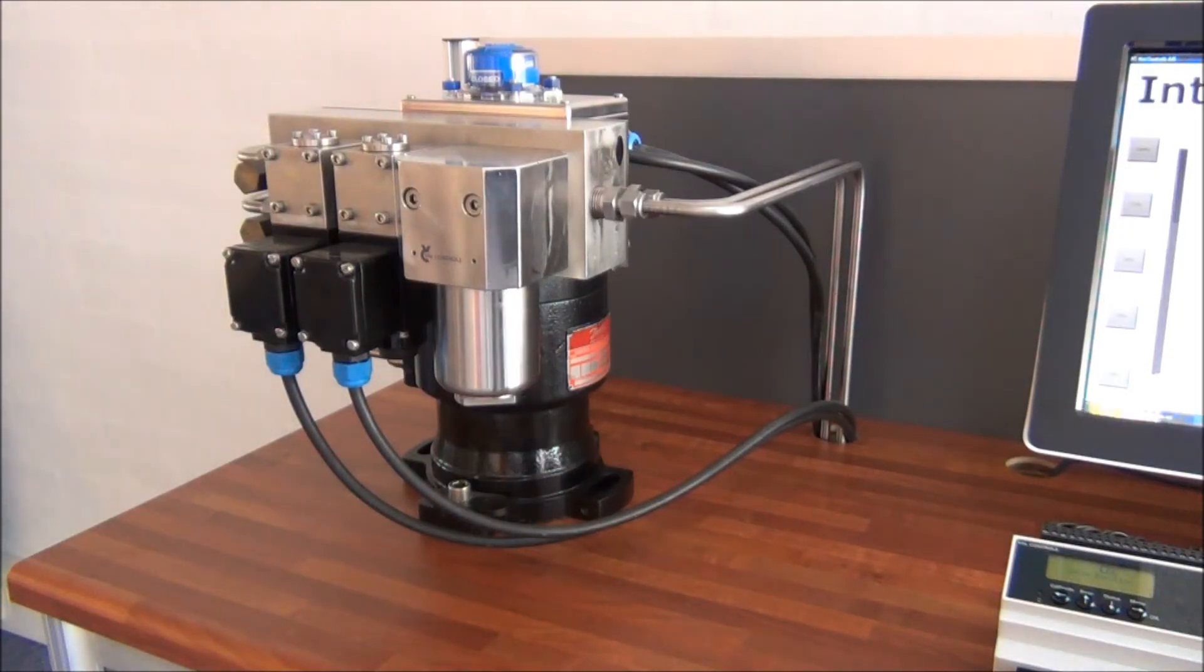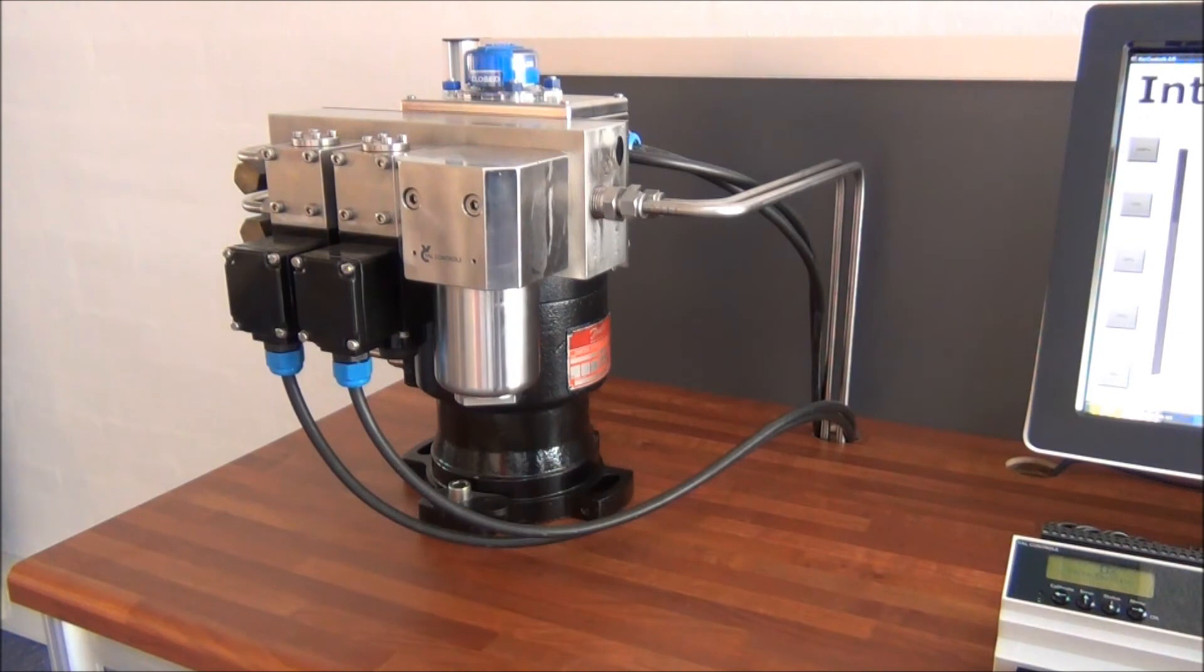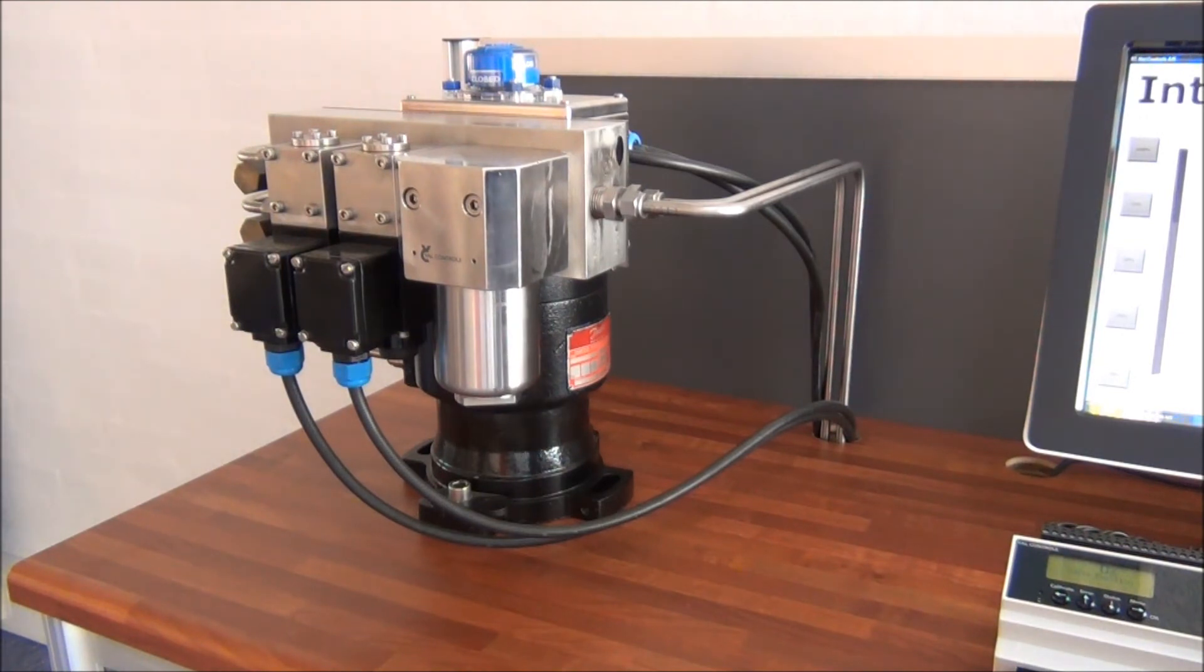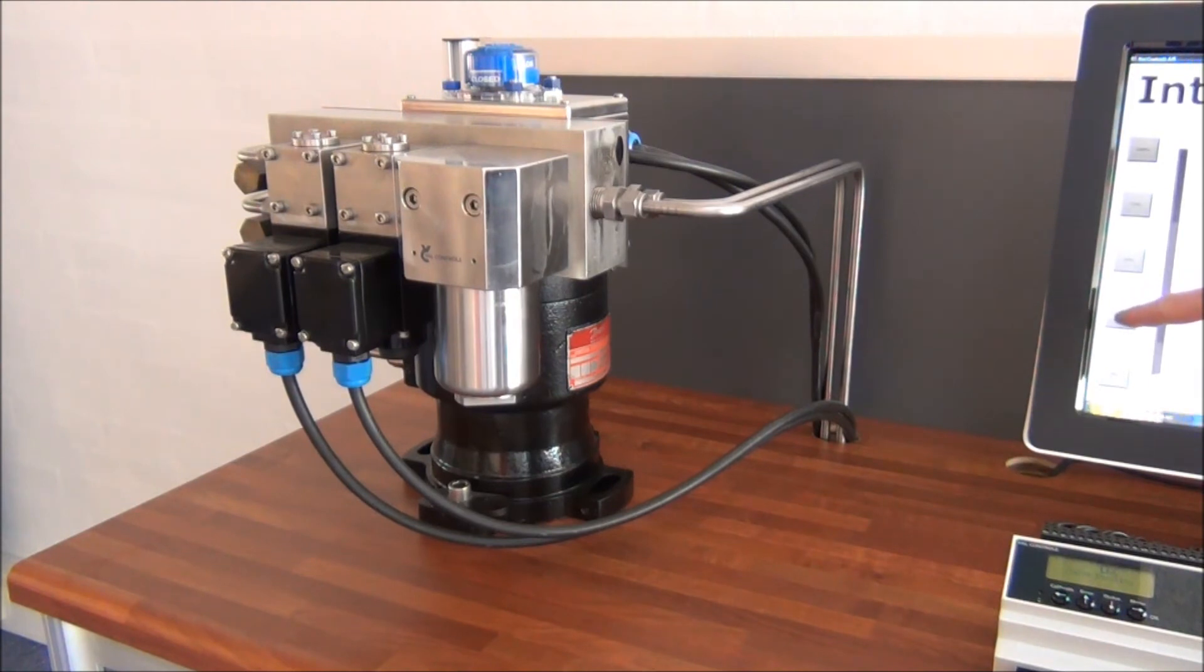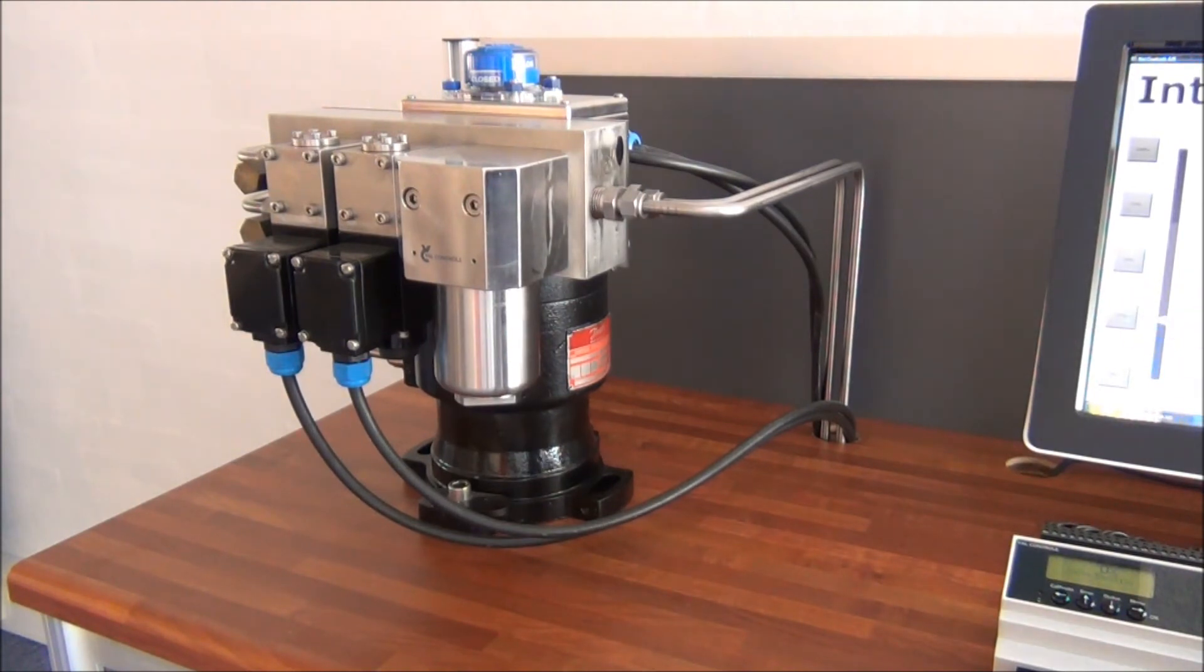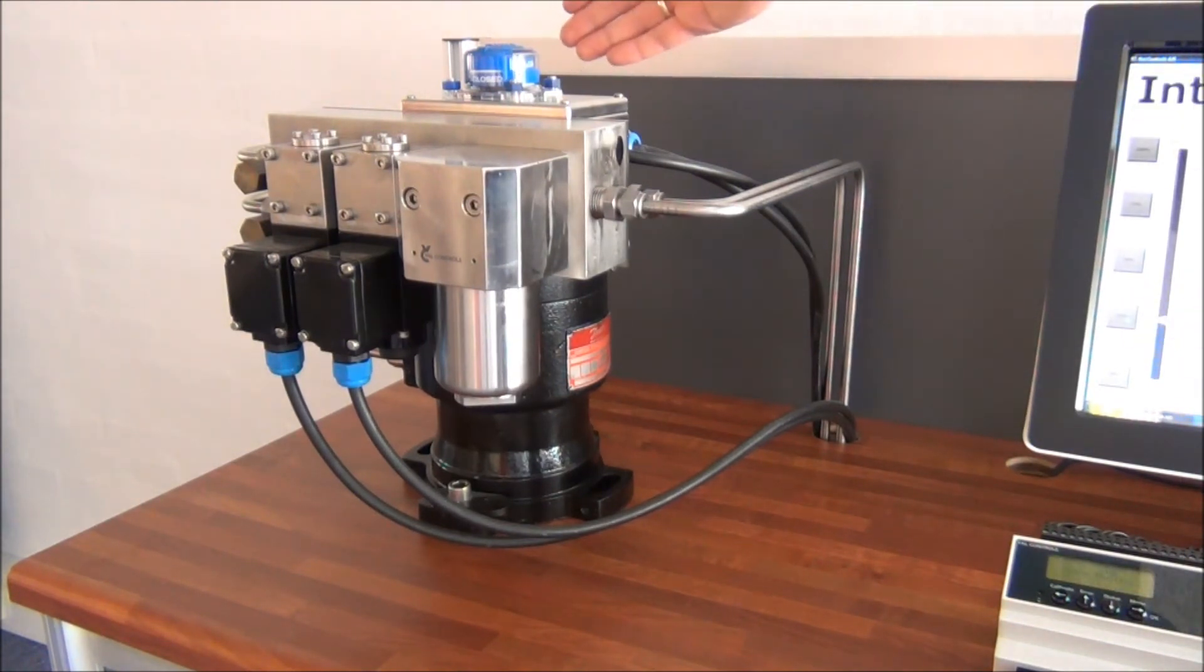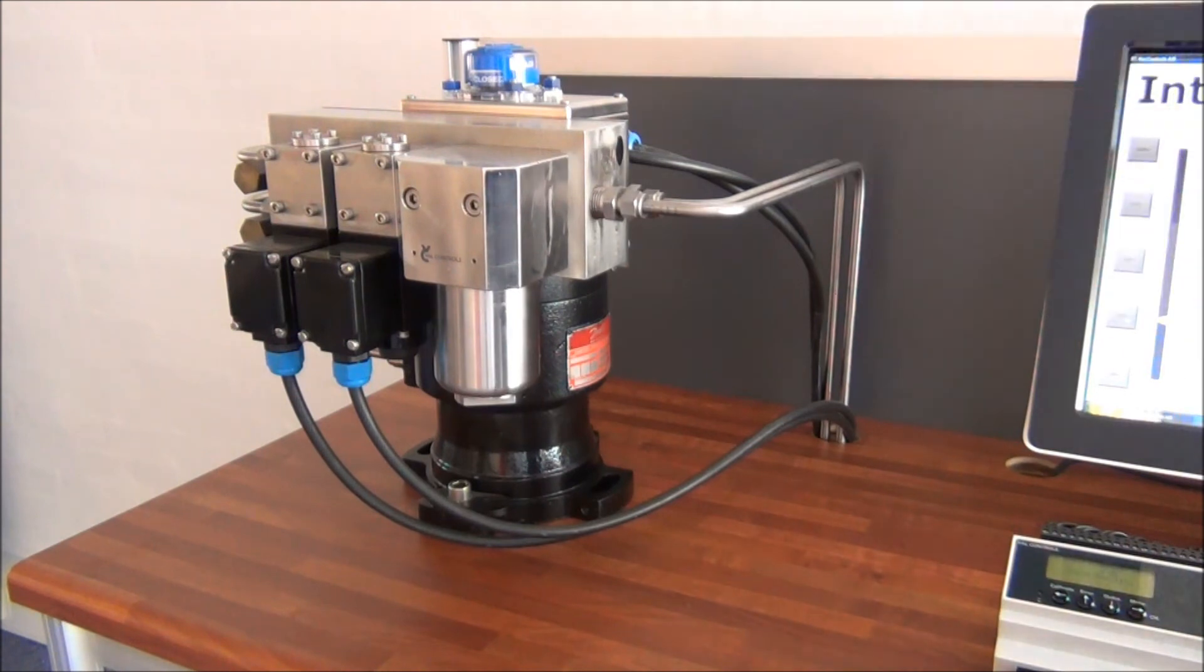Now the unit has finished its calibration and we can start using it. First I'll tell it to go to 25%. We can see on the indicator on the actuator that it starts moving and it goes to 25%.